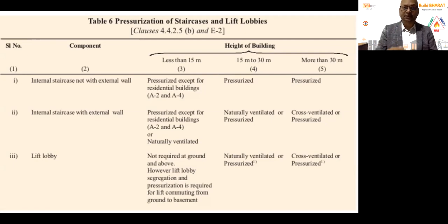But if you look at table 6 in NBC, it doesn't give complete clarity on pressurization or not. There are many areas where you have a naturally ventilated corridor, but your lobbies are air controlled. Your stairwell is naturally ventilated, but your lift lobby is pressurized. So how do you manage it? You need to do a performance-based design, creating a differential pressure such that if your lobby is pressurized, your stairwell must also be pressurized.